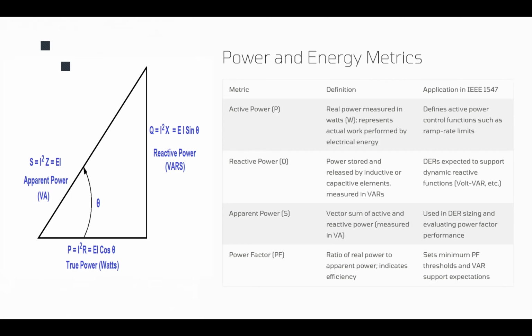Okay, for example, we could have a 100 kilovolt ampere inverter, which provides 80 kilowatt real power. But it still needs to supply plus or minus 44 kilowatt reactive power, which means when we want to define that, we say that inverter needs to provide 44% of rated apparent power based on IEEE 1547.